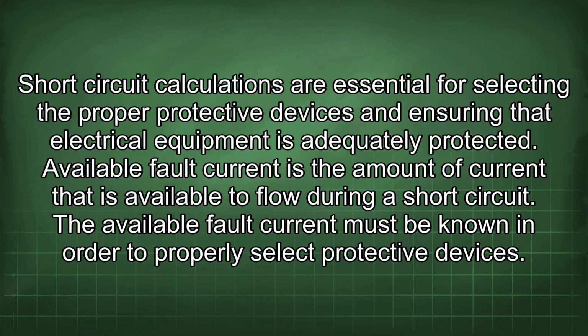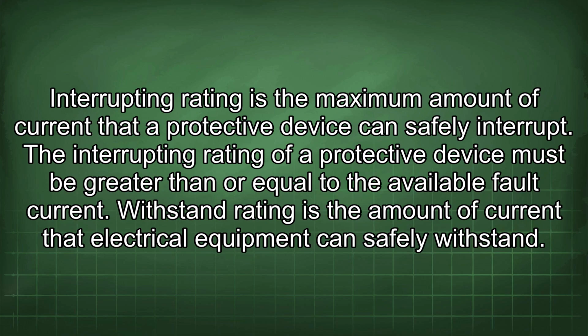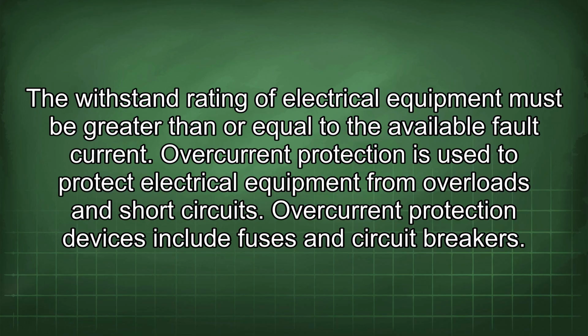The available fault current must be known in order to properly select protective devices. Interrupting rating is the maximum amount of current that a protective device can safely interrupt. The interrupting rating of a protective device must be greater than or equal to the available fault current. Withstand rating is the amount of current that electrical equipment can safely withstand. The withstand rating of electrical equipment must be greater than or equal to the available fault current.